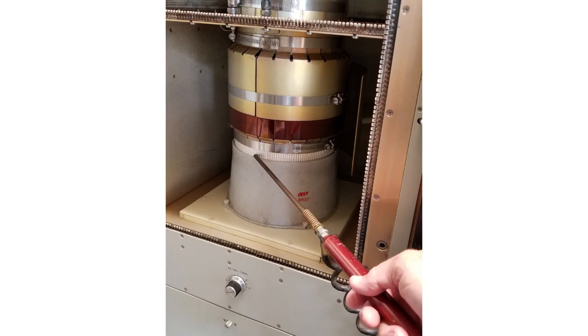There are interlocks in the transmitter, and we'll look at them in just a second here, that are supposed to help bleed off this voltage and keep it from ever being there in the first place. But this is a safety precaution here because those will stick sometime and don't work just right. And you can't afford to make a mistake there. So what you see in there that the stick is touching, that's the plate of a 4CX-15000. Right above it, that kind of maroon color is an insulator. And above that, that's a gold-anodized aluminum. That's the plate-blocking capacitor. So that's how it gets the RF off of the tube on up to the transmission line to go out.